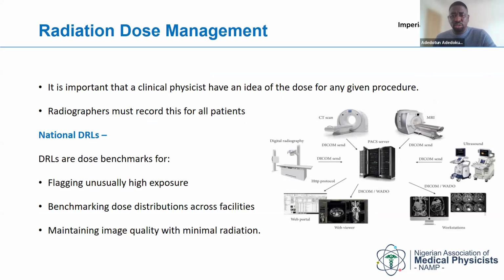If it's something where, sincerely, you don't know what is going on, then you call, but what you know is that this equipment should give this. You're setting your equipment, your mobile X-ray for example, on 70 kV and 5 mAs, and on your dose meter you're measuring 78, 79. That is beyond specifications. You might not be able to fix that as a physicist. You won't carry a screwdriver and unscrew the system. Then you need to tell the engineer or the application specialist that before we can put it to use, you have to bring the kV within this range.